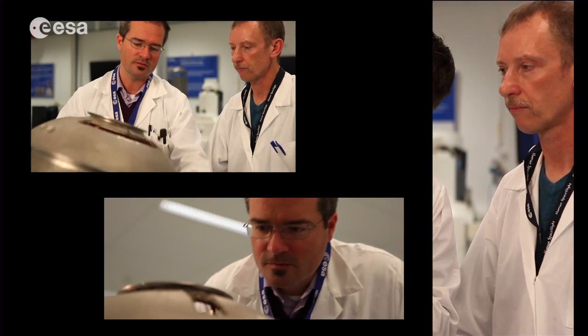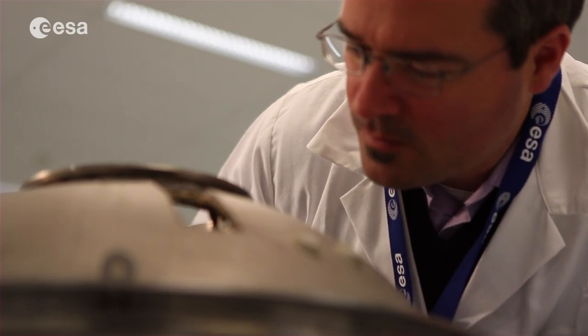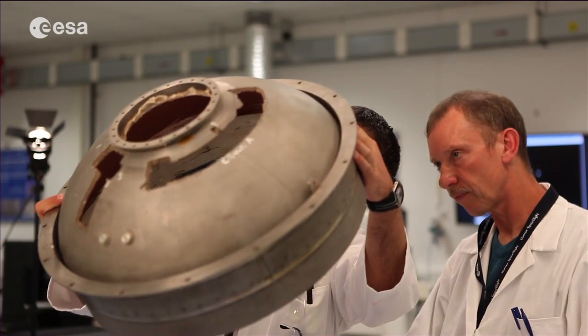When we got the sample here, we looked at the fracture surface and we could see that some parts of the fracture surface became very brittle and couldn't withstand the pressure of the tank.